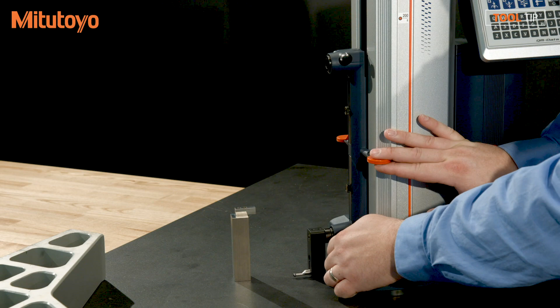Perfect. Drew, as you can see, there's 2 positions on the slider. The probe is currently in the lower position, and I want to move it up to the top. So I'm going to hold the slider so that it doesn't pull back up with the counterweight when I remove the probe. Now there's a little notch or an indentation on the probe that I'm going to line up when I insert it into the top slot to make sure that it is oriented correctly. I'm going to go ahead and lock that down. So this will keep you from putting it in incorrectly? Yeah, it's meant to be used either in an up position or a down position. At a different angle, you're not going to get the rigidity that you need to get accurate measurements.